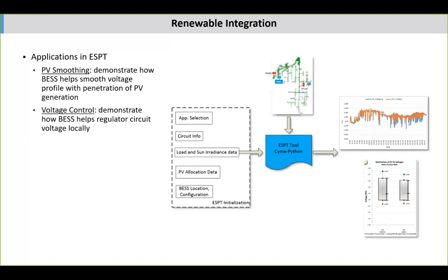In order to do this, you need to understand the circuit, be dealing with that planning model, understand the irradiance data that's applicable to the PV on the circuit. Ideally, you'd know things like the orientation of the panels and how much tree cover. Real world, no, you don't know these things. Knowing where the PV is about the best you can hope for. But the idea is to bring the voltage level variation within ANSI standard - in other words, not to bring it to nominal, but to bring it within 5% of nominal.